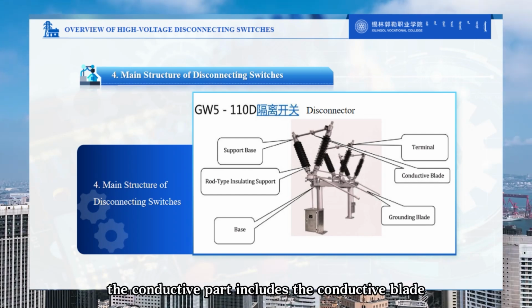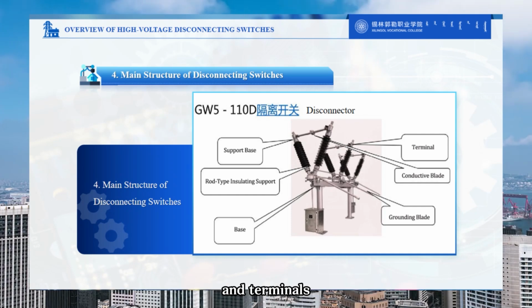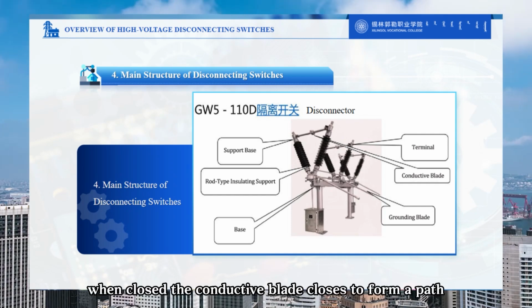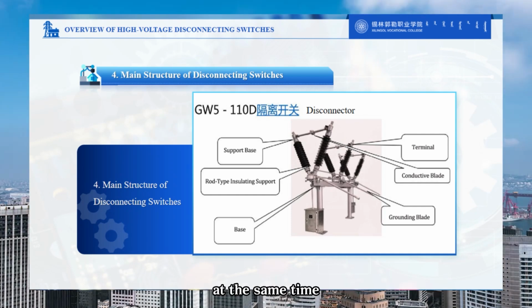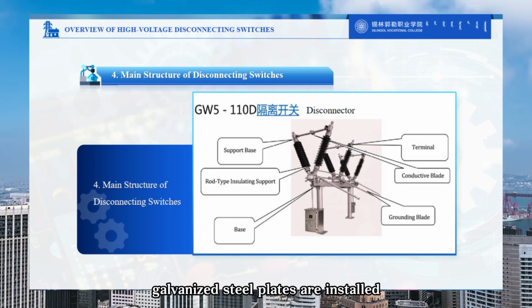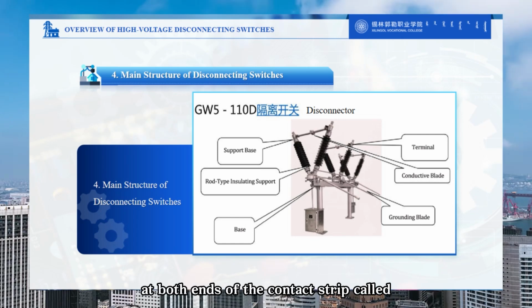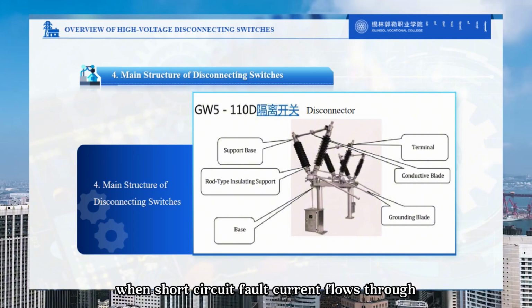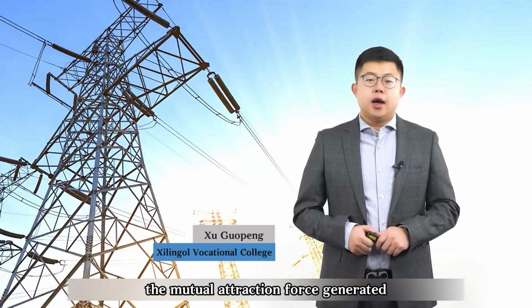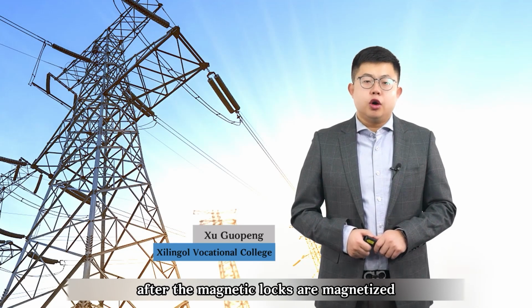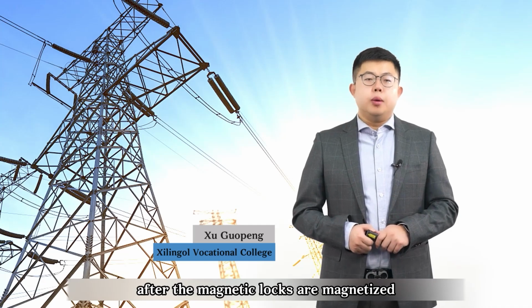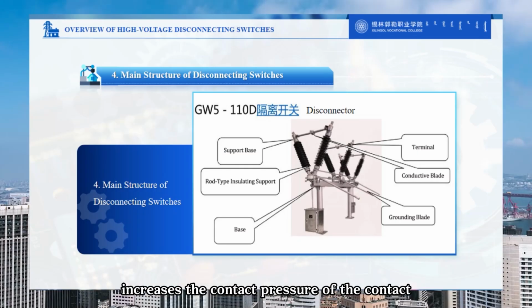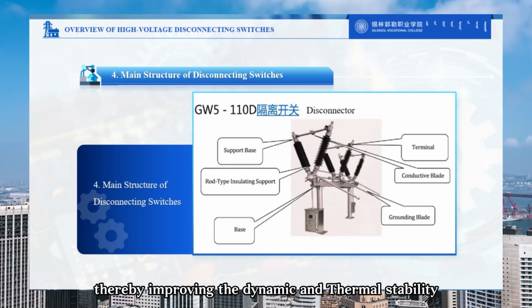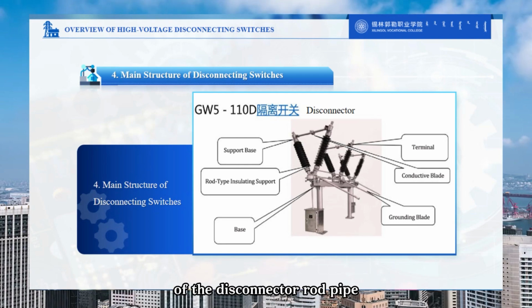The conductive part includes the conductive blade and terminals. When closed, the conductive blade closes to form a path. Galvanized steel plates are installed at both ends of the contact strip, called magnetic locks. When a short-circuit fault occurs, current flows through, and the mutual attraction force generated after the magnetic locks are magnetized increases the contact pressure of the contact, thereby improving the dynamic and thermal stability of the disconnector.